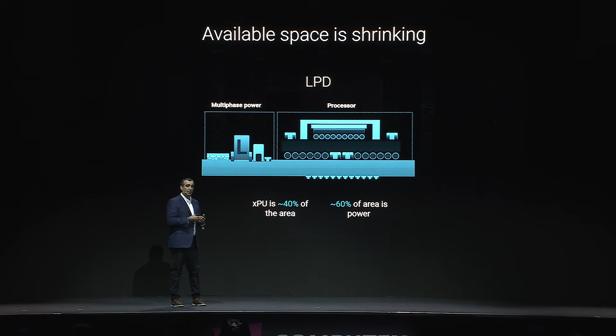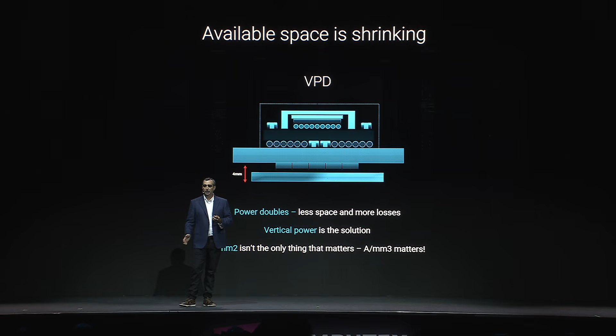Let's think about how power goes from the grid all the way to the gates of the processor. Today, this architecture has changed. What it used to look like is an AC to DC conversion to a 48-volt backplane up the entire rack to the processor, 48 volts. That worked fine until we needed a 1 megawatt rack, which would require over 20,000 amps of current up the backplane. Unfortunately, the laws of physics are real, and it doesn't work.